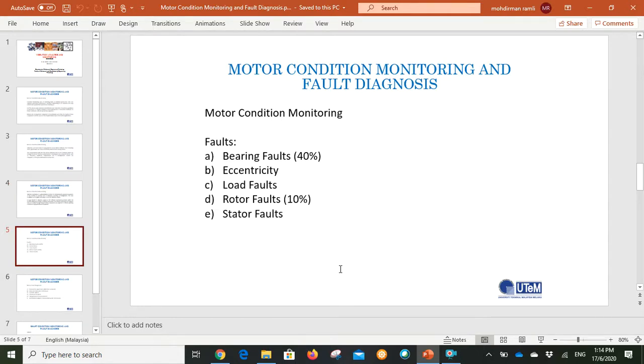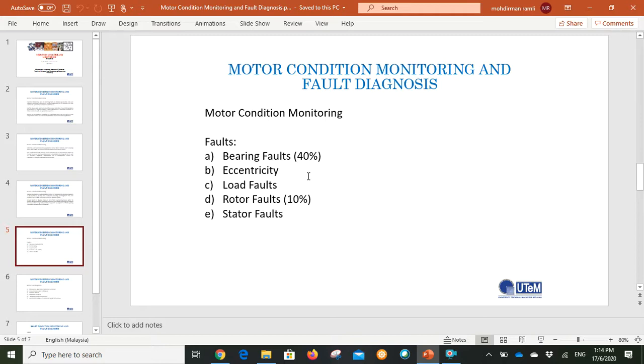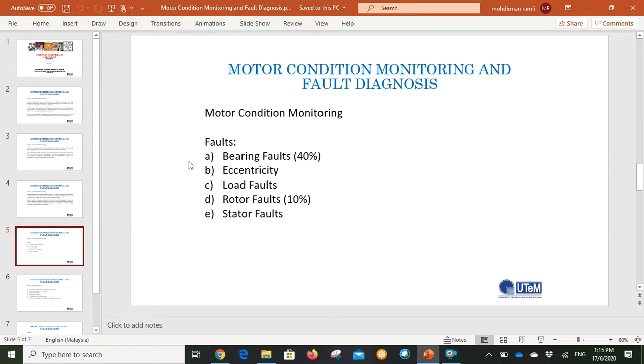When we do motor monitoring, the types of damage usually found are: bearing faults usually represent 40% of all damage, eccentricity problems and load faults, rotor faults which usually represent 10% of total damage, and also stator faults. These five faults commonly occur in motors.